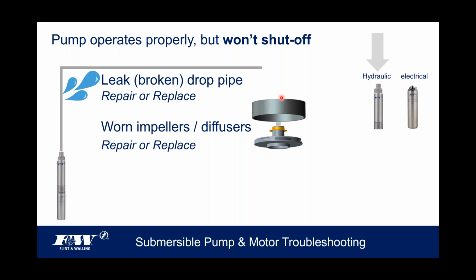And when we talk about replace, I'm talking about the whole pump assembly. Very few people go inside a submersible pump end these days and do any kind of repair work at all. Most of the submersible pumps you purchase today, you couldn't get inside that wet end if you wanted to. They're not threaded together anymore. The discharge is crimped in, the motor mount's crimped into the pump end, and you can't get in there unless you want to cut it apart. But nonetheless, if a pump won't shut off, there's no leak in the drop pipe, and the pressure switch seems to be functioning fine, I'm going to start looking at these impellers and diffusers and make a call on whether they're clogged with iron, sand, or debris, or whether they've just flat worn out over time.